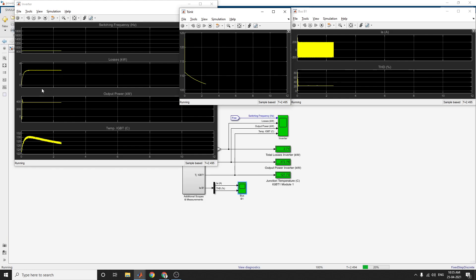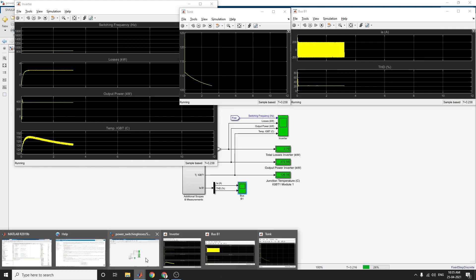From time zero to five seconds, the inverter output is 372 kilowatts with a power factor of 0.85. The total losses are 2.70 kilowatts and the output power is 372.37 kilowatts, as shown in the scope.